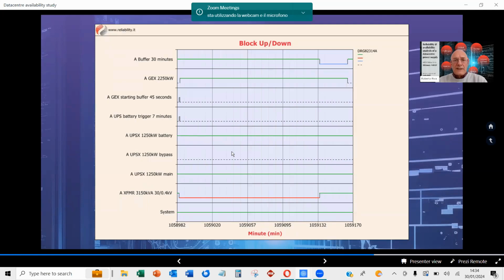We got a different testing. This is a testing of a failure of transformer A on system A. So transformer A is out of use. And we got the battery coming in, and then we got the generator 40 seconds later. Generator comes in 40 seconds later, and then we have a buffer of 30 minutes because it was a requirement. We want to make sure that after the fault has been cleared, the generator will stay on for another 30 minutes. So we put in this buffer time of 30 minutes.